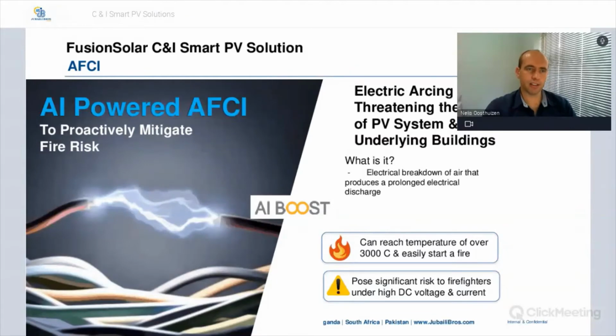Moving over to the next slide is the AFCI. I already said what it is. So AFCI is an arc fault circuit interrupter. And what is it? It's an electrical breakdown of air that produces a prolonged electrical discharge. It can reach temperatures of over 3,000 degrees Celsius, which can easily start a fire. So it poses a significant risk to firefighters under high DC voltage and current. We are all familiar, or most of us should be familiar, with the difference between DC and AC. If you look at a DC arc, it takes a lot longer to extinguish versus an AC one. So this is definitely a high risk, and a good feature that has been incorporated into the Huawei inverters is this proactive mitigation of the fire risk, the electric arc fault detection.